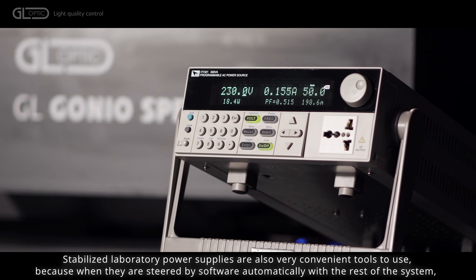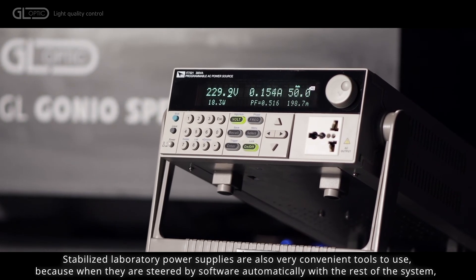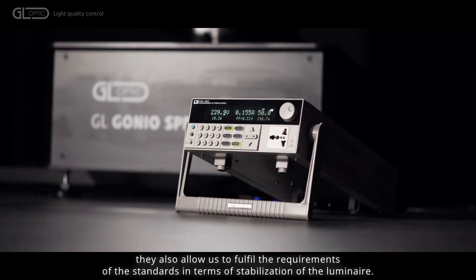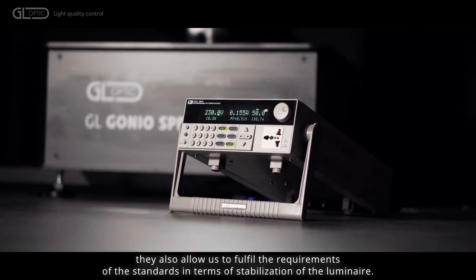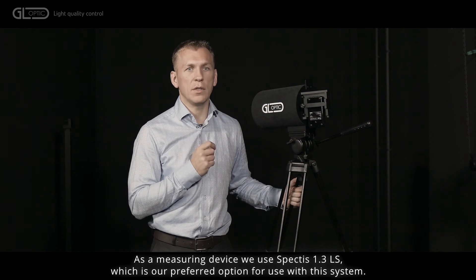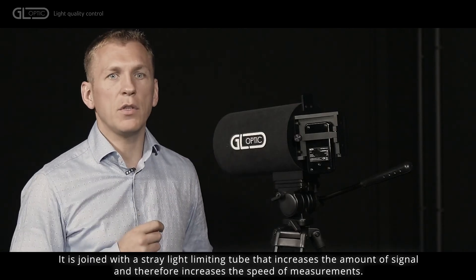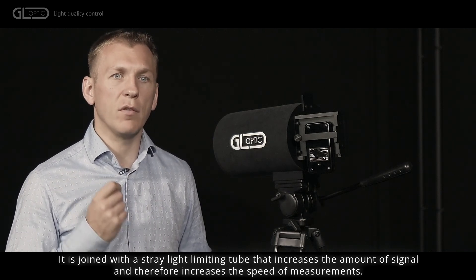Stabilized laboratory power supplies are also very convenient tools to use, because when they are steered by software automatically with the rest of the system, they also allow us to fulfill the requirements of the standards in terms of stabilization of the luminaire. As a measuring device we use Spectis 1.3 LS, which is our preferred option for use with this system. It is joined with a stray light limiting tube that increases the amount of signal and therefore increases the speed of measurements.